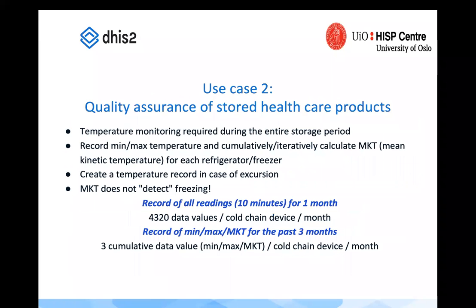Next slide, please. So quality assurance: it's also important to have a record of the temperature throughout the lifetime of drug products, ideally from the manufacturing site until the child is vaccinated. So we would cover part of that.